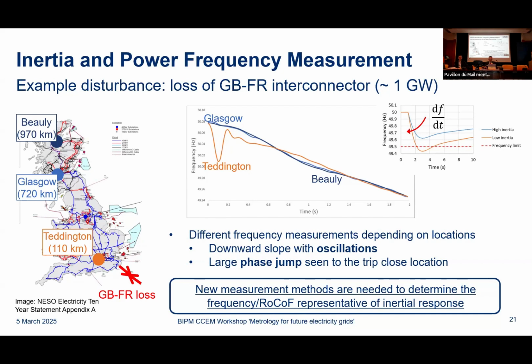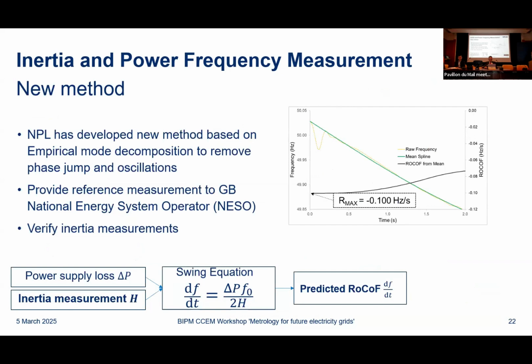And one of the questions that in this project we were trying to answer is, well, if we want to characterize the inertial response of the system, then really the frequency measurement should tell us what it is. So how do we get a frequency measurement from these 3 measurements that's reflective of this inertial response? And so this really is just to show that frequency measurement isn't necessarily a straightforward thing to do, depending on the dynamic situation that the power system is in. And so we've been doing some work basically to look at, well, how can we remove some of those transient effects to obtain a frequency trajectory that is representative of this inertial response in the power system.